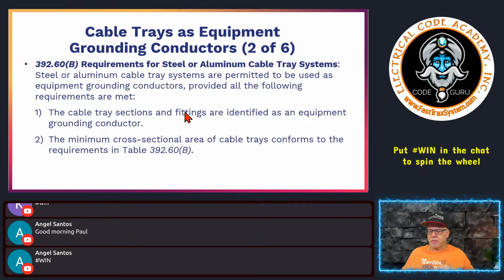Okay, now let's talk about what we just saw. That was the general statement, the general rule talking about the use. It's permitted to use a metal cable tray as an EGC. Now we have specific rules we have to follow if it's a steel or aluminum cable tray system. It says steel or aluminum cable tray systems are permitted to be used as equipment grounding conductors provided all the following conditions are met. Not some of them, not part of them, but all of them.